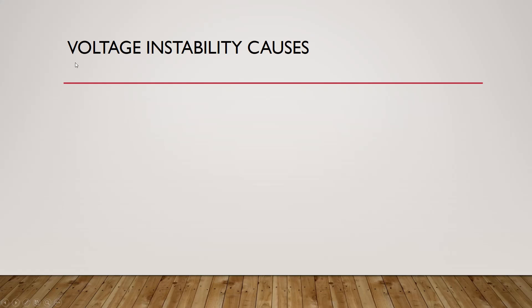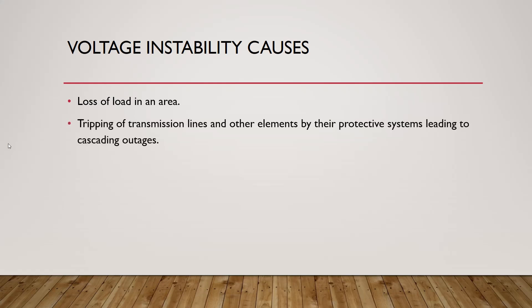In the case of voltage instability, the following consequences occur. Number one is loss of load due to a decrease in voltage. For example, for induction motors: when voltage decreases and the same torque is required, the induction motor will absorb more current to satisfy that torque demand, causing overheating. The thermal protection will then trip the induction motor.